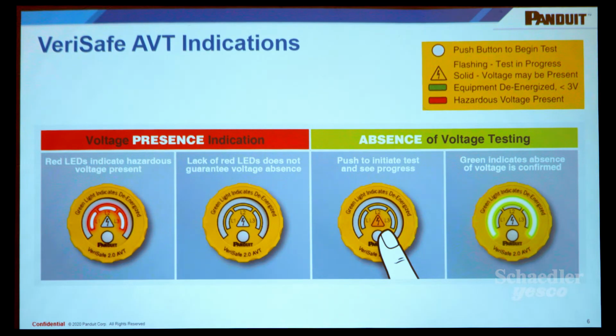Then if the panel is safe to enter, and safe to enter is qualified by UL as 3 volts or less, it gives you a green indication. Now, if it's not safe to enter, the yellow hazard light will flash a certain code. So if there's voltage above 3 volts, or if there's not enough power to complete the test, or if the self-diagnostics failed for some reason, the indicator module will tell you as well. At that point, you just go to your traditional manual test and do a traditional live, dead, live test.